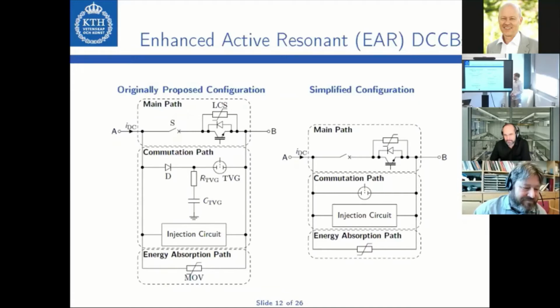There are also some solutions arranged so that the injection circuit is pre-charged from the DC line. But then there are also, most likely, some mechanical switches to reconfigure the injection circuit to allow a path to ground. The triggered vacuum gap has a triggering unit, which also has to be energized. An option here could be using a discharge closing switch with laser triggering, so one only has to supply the laser, and the triggering unit is galvanically isolated.